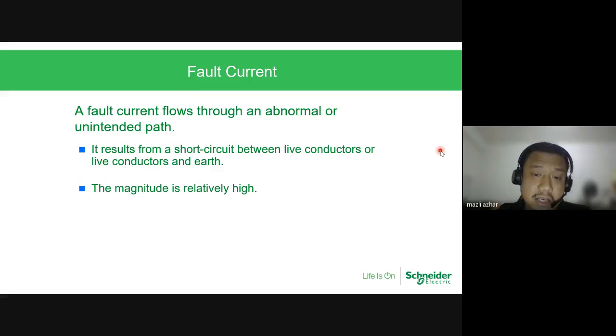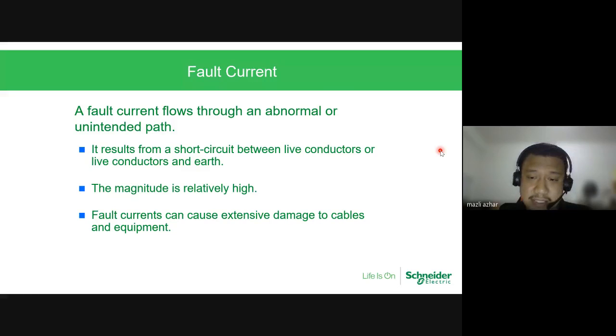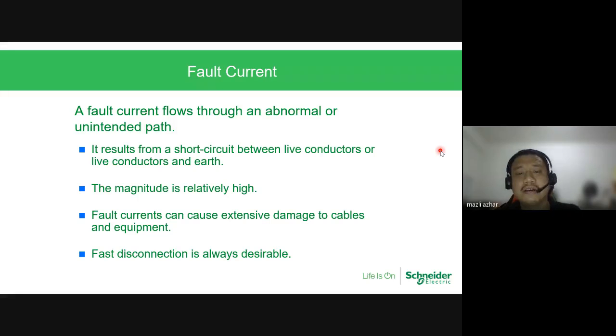So if you recall back my slides, I showed you the marking of each of the breakers. They have 4,500. So this is where the magnitude has to be catered for, because if you say, oh, it's just a 16 amp breaker, but when there is a short circuit, it can go to 4,500, 6,000, 10,000 amps in a blink of an eye. And fault current can cause extensive damage to cables and equipment. And fast disconnection is always desirable. Why? Because to ensure there is no bad thing that happens to the cable or to the equipment or to the people themselves.